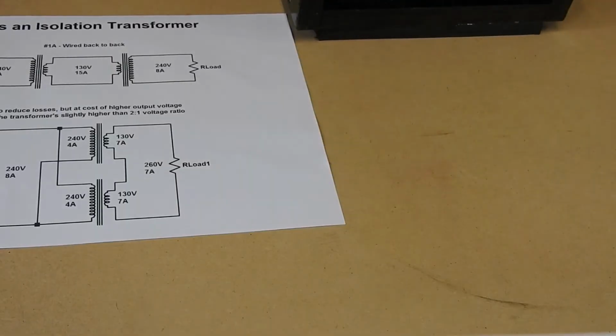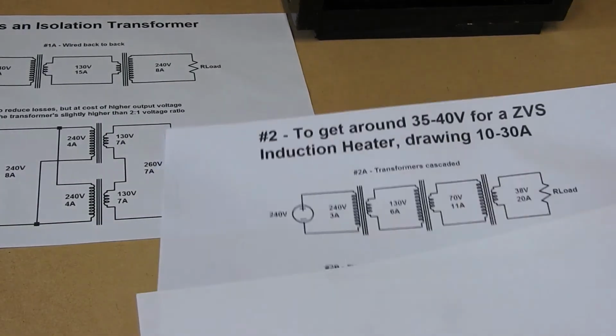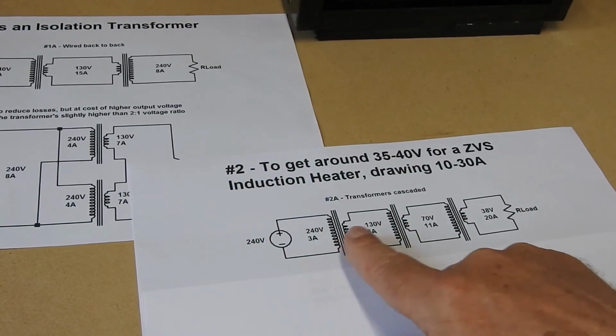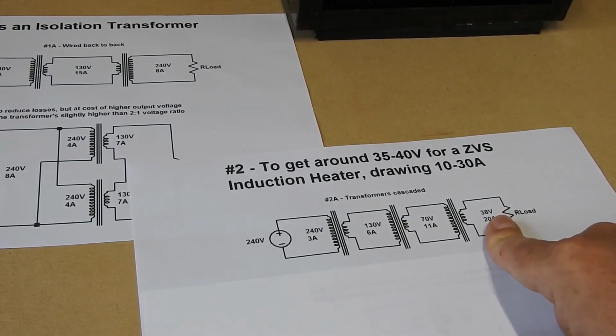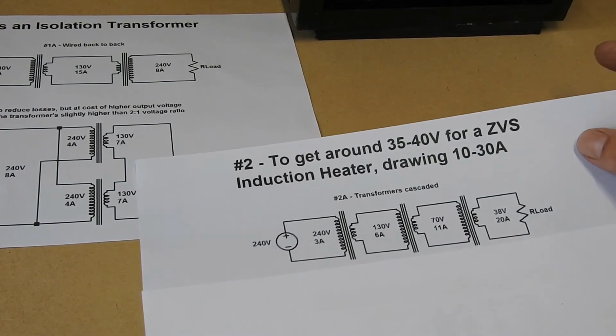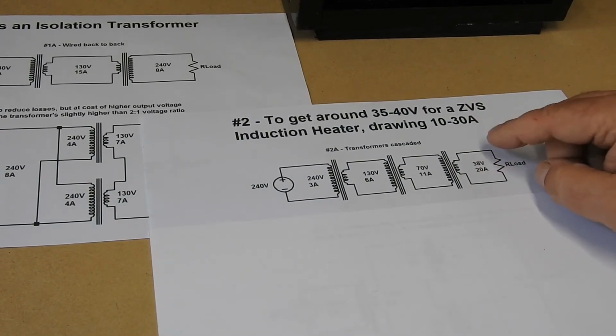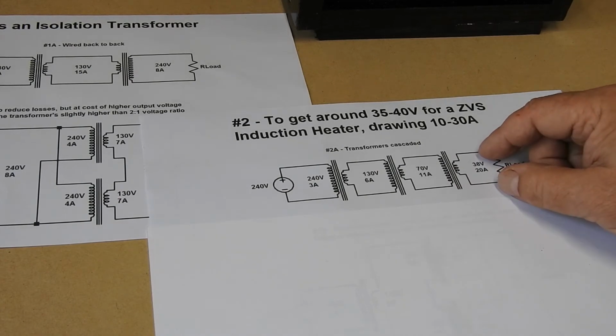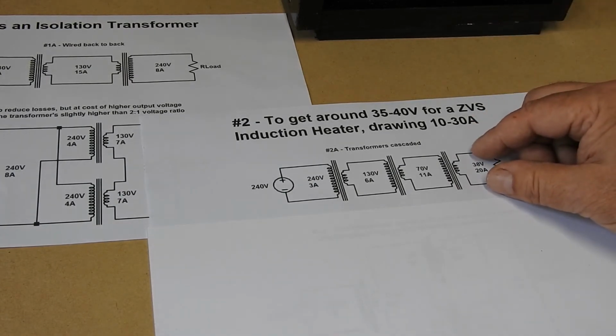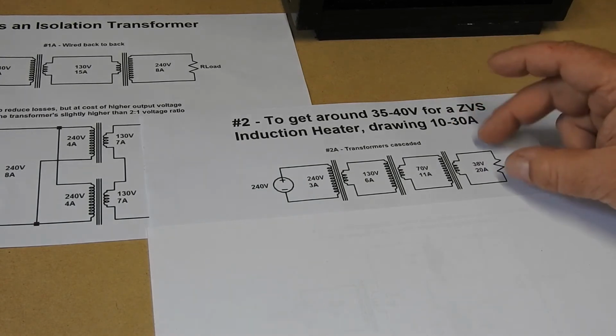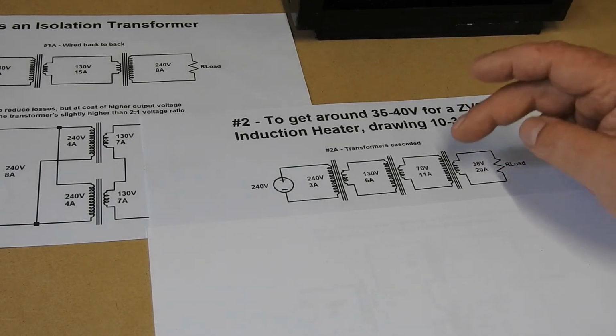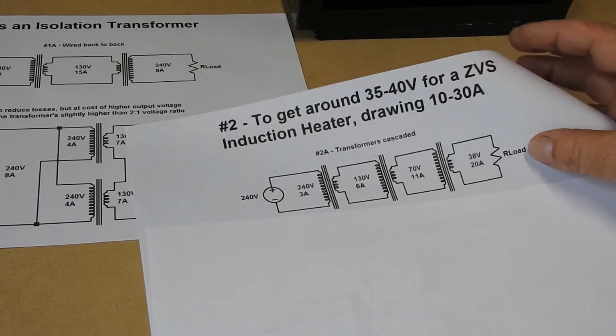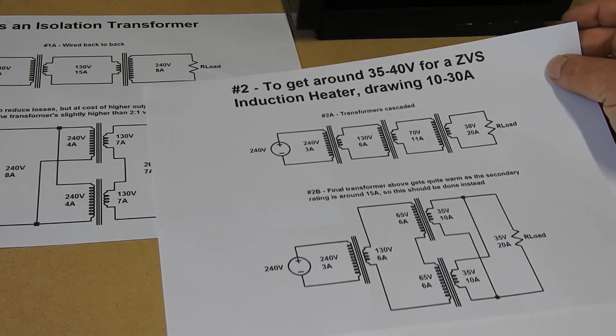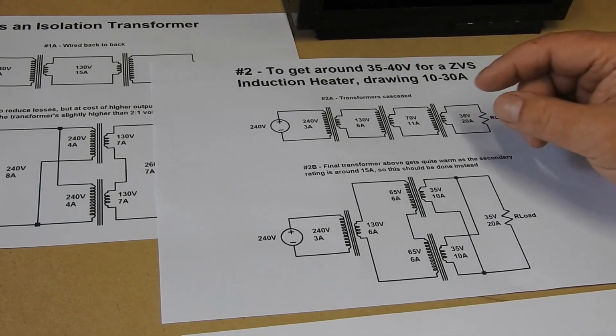In the other example, where I put 3 of them in series, cascaded to get 40 odd volts, it was like this. So we had 240 down to 130, down to 70, down to about 38. And again, there's a better way of doing that, because the final secondary, given 2 kilowatts, should be about 15 amps rating. So 20 amps or even 30 is way above. And in fact, this final transformer was getting very warm, bordering on hot. So the way to handle that would be to do this instead.